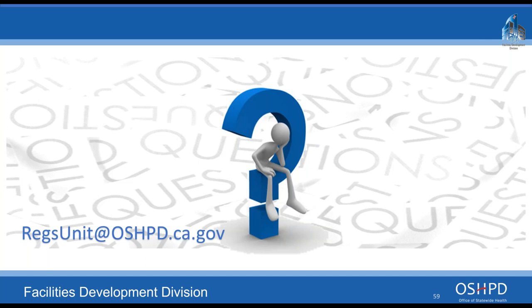There is language in ASHRAE 170 about redundancy of boilers providing hot water, and I'm sorry, I don't have that verbiage off the top of my head right now specifically. But hopefully I'm answering that question. Redundancy is very, very simple. If you take one thing out, the rest of the remaining equipment has to be able to carry the load. Now, there are some standalone instantaneous water heaters where we have storage tanks associated with those water heaters. The redundancy in that case does apply to the tanks. If you have three instantaneous water heaters all filling one tank, and that tank goes down, you're not serving the facility correctly. I hope that makes sense. Very good question. It does come up once in a while.